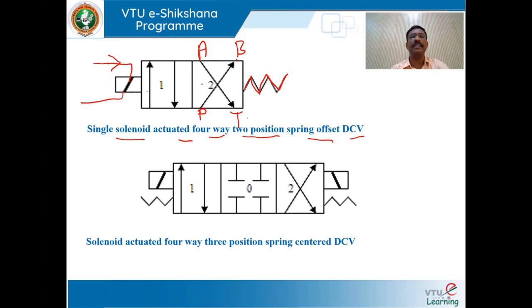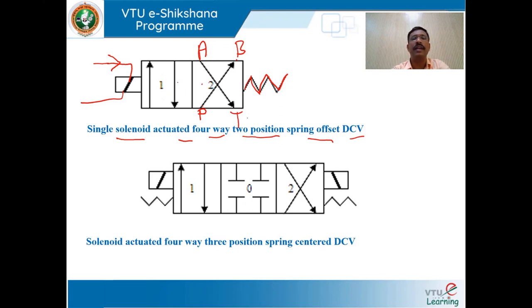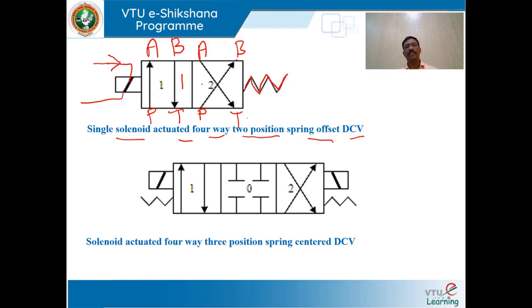When current is supplied to the coil and the coil is energized, the spool moves to the left envelope configuration, causing port opening and closing — P is open to A and B is open to T. This is how to draw a symbol for a single solenoid actuated four-way two-position spring-offset directional control valve.